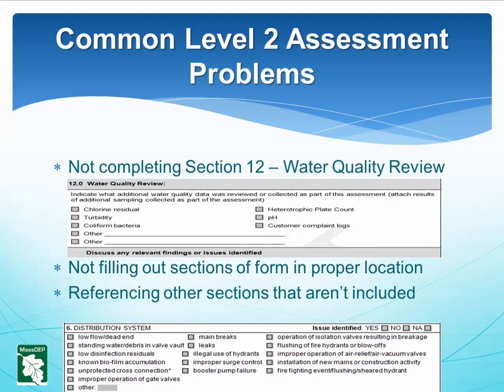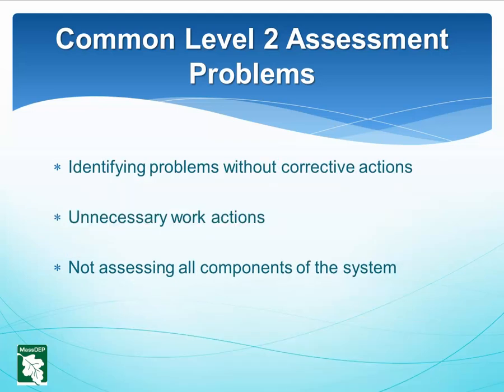More Level 2 problems include not filling out sections of the form in the proper location — in the boxes on the pertinent sheets — and referencing other sections where additional details should be but are not provided. For example, one assessor stated 'see action plan' rather than describing the issue in the form. It is helpful to attach supporting documents, but the assessor may not skip sections. Additional problems include identifying problems in an earlier section without corrective actions, proposing work actions after no sanitary defects were found, and not assessing all components of the system. When asked whether the well cap vent was screened, the response 'could not access well cap' is not acceptable — all components of the system should be accessible.